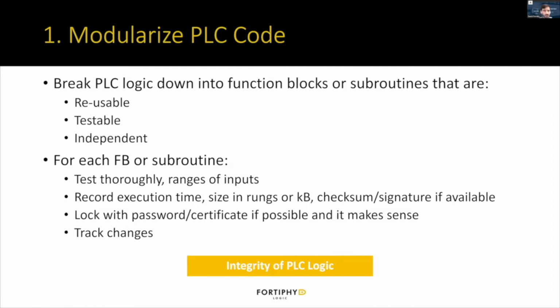All right, so finally getting started. Looking at the first practice. The first practice is modularizing PLC code. So a great intro, the previous presentation by Russ, looking at object-oriented practices for PLC programming. This is basically the same thing. For this, we're breaking down PLC logic into function blocks or subroutines, primarily trying to make them reusable, testable, and independent. So that for each function block or subroutine, you can really thoroughly test. You can focus in on that function block or subroutine, test the range of inputs and all the corner cases of the different potential bad values that might be coming in, and make sure your code handles it safely and in a predictable way.